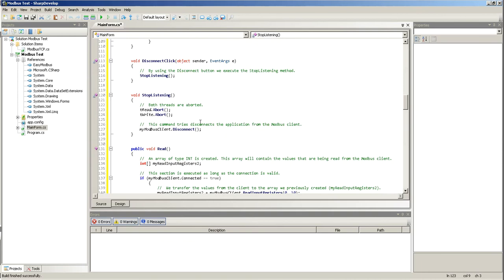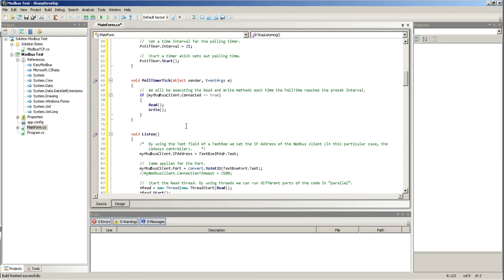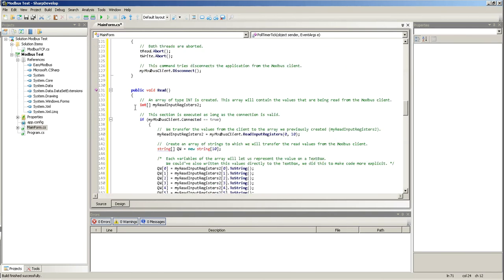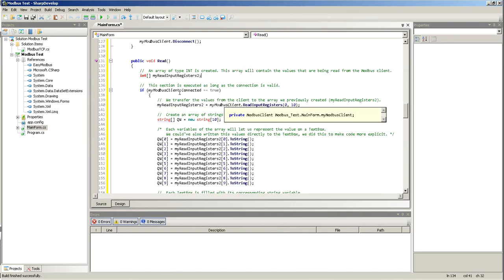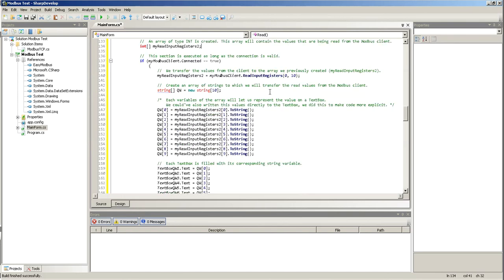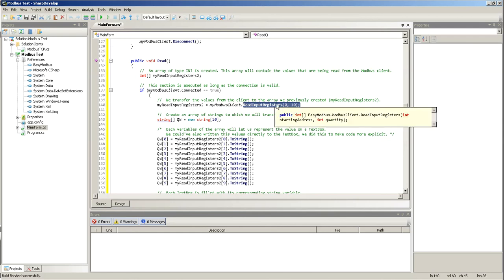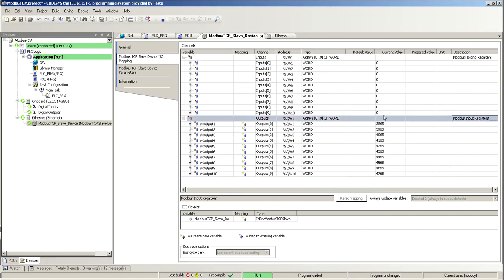So, when do I execute my read? I execute my read up here, here. So, I execute read every 25 milliseconds. So, read, and what that happens is, first of all, I create an array of integers, and then if I do have connection to the client, what I do is I execute read input registers. By reading the input registers, basically what I'm doing is, I'm reading this, trying to read what the PLC is sending.